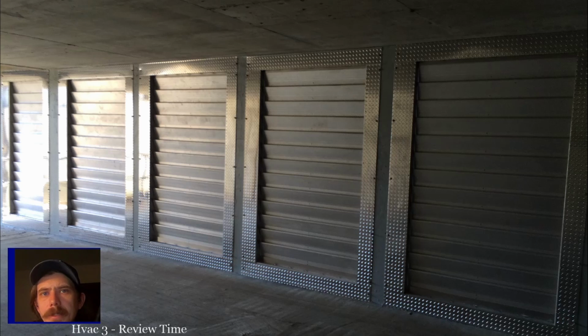basically two different grades of ECM, and people get them mixed up sometimes, and even I do when I'm talking about it as I'm reading through this section. You have an X13, all right, which is a constant torque motor, and that is one that you would use to replace a PSC motor. And then you have your actual variable speed ECMs, whose controllers are complicated enough that it's matched with the equipment it's being used on, so that you can maintain a certain speed or a certain airflow rate based on what's going on with the system.